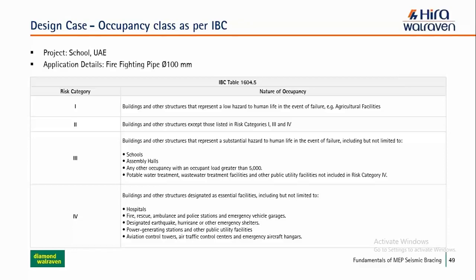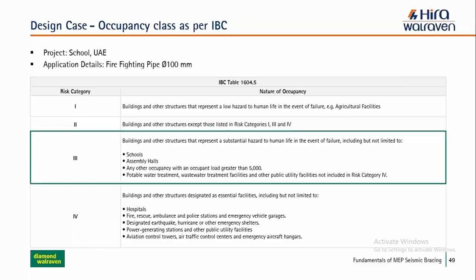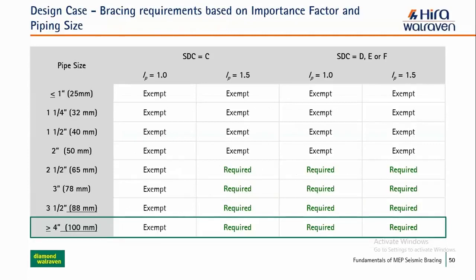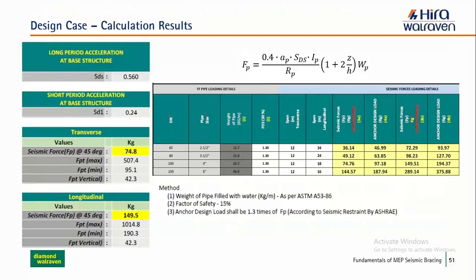Let's say we have one school, and this school comes under risk category 3, and the nature of occupancy is 3 for these schools. Then let's say we have a pipe of 100 mm diameter, which is a firefighting pipe. Let's go again to this table, which shows the requirement if the seismic design category is D, E and F, and if the seismic design category is C. Here is the requirement: Ip is required in all cases. So now we have some calculation for this pipe along with the other sizes as well.